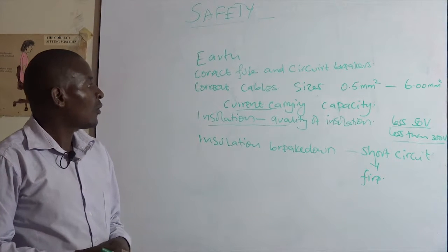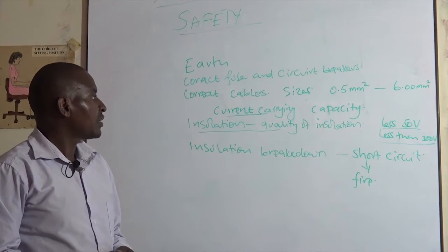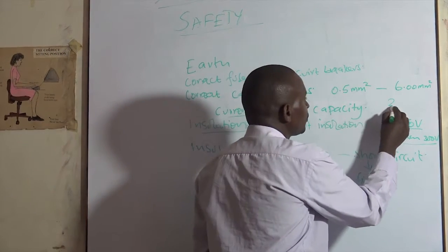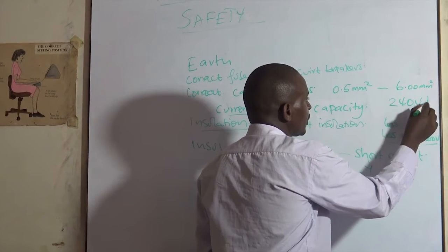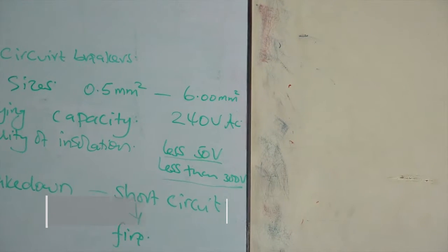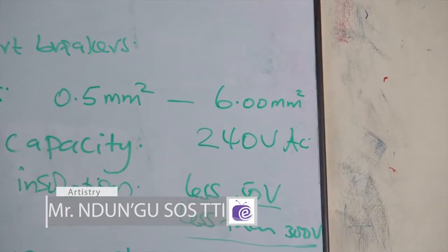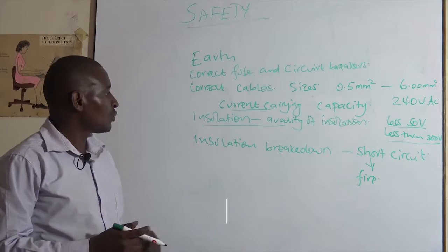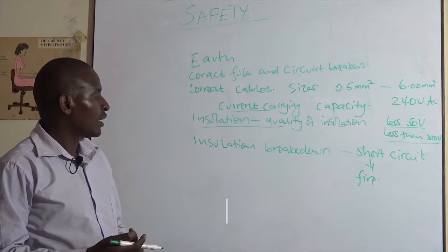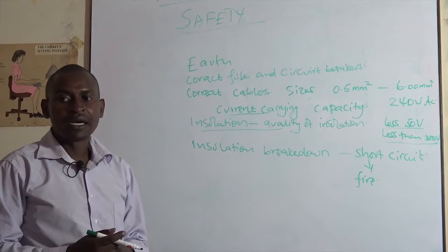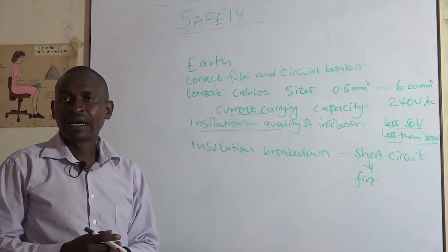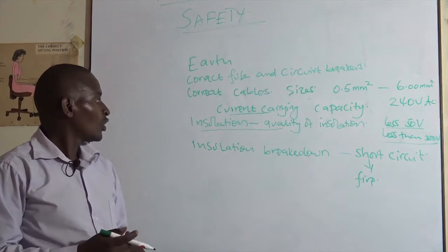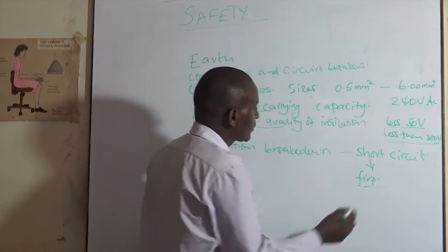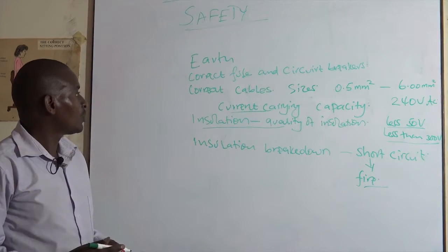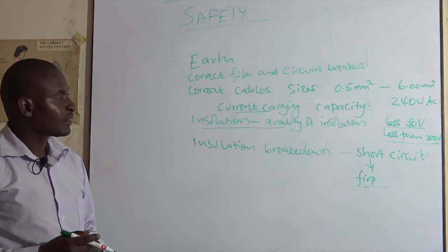Now in Kenya, our main supply is 240 volts. They are rated at 240 volts AC. Now, if you use a cable whose insulation is only guaranteed up to 50 volts, then you are exposing yourself to insulation breakdown and probably a short circuit. And if the short circuit is not taken care of, then the risk of fire is quite high. So this goes a long way to give you an insight into the risk that you are exposing yourself to.